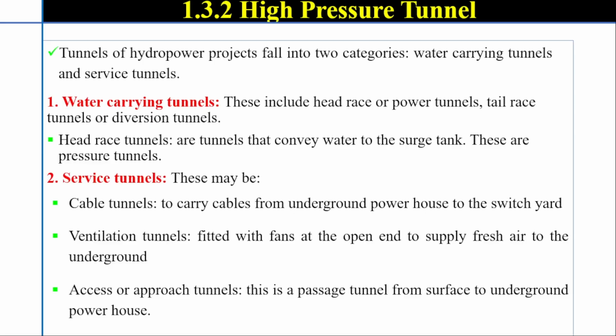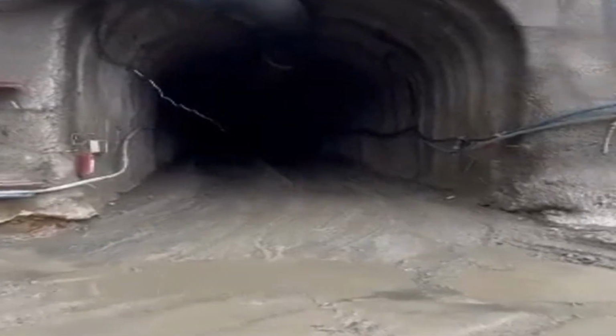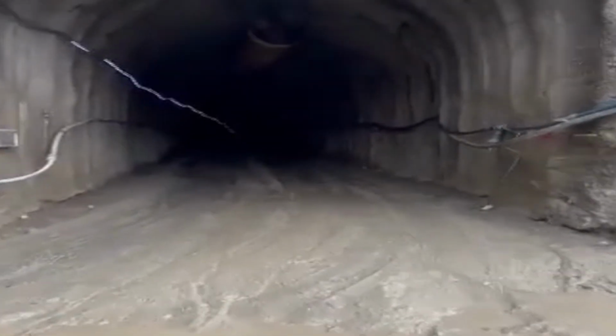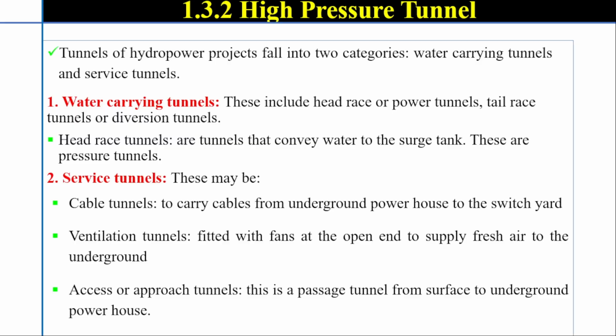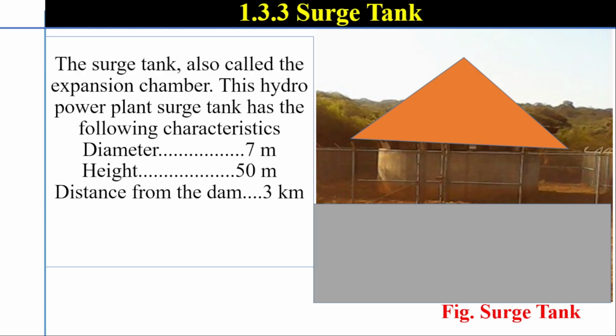Head race tunnels are tunnels that convey water to the surge tank. These are pressure tunnels. Service tunnels may be cable tunnels, ventilation tunnels, adits or approach tunnels. Cable tunnels carry cables from the underground powerhouse to the switch yard. Ventilation tunnels are fitted with fans at the open end to supply fresh air to the underground. Adits or approach tunnels are passage tunnels from the surface to the underground powerhouse. Surge tank.